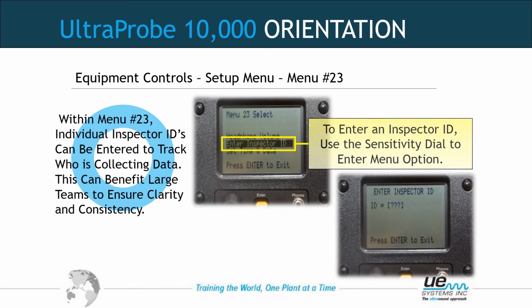Enter the inspector ID, who took the reading. If we are trending and trying to be repeatable, we certainly want to know who took the reading. It's 3 alphanumeric characters. Maybe it's their initials. Once you enter this, it will store it on every single record taken. If you do this on the baseline, it will keep moving it back and forth between the software and the Ultraprobe until that is changed as that person taking that reading.